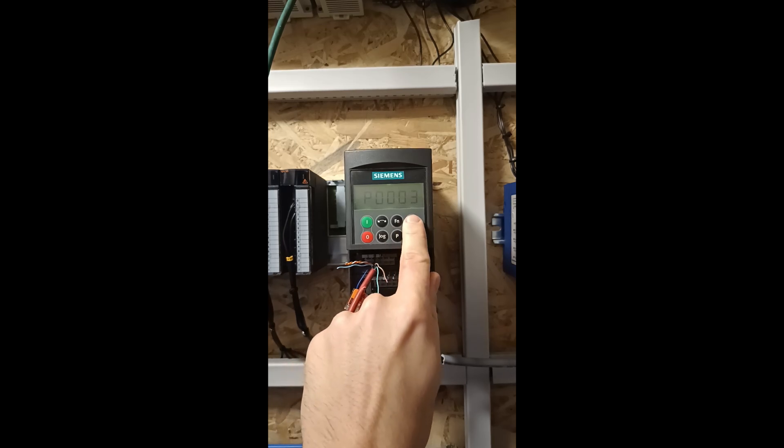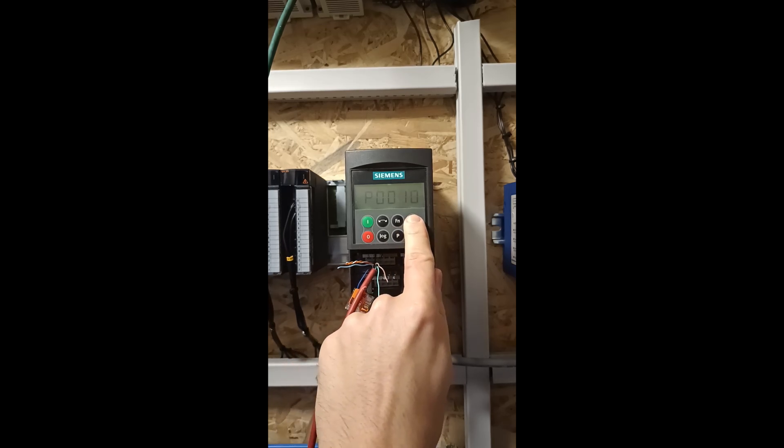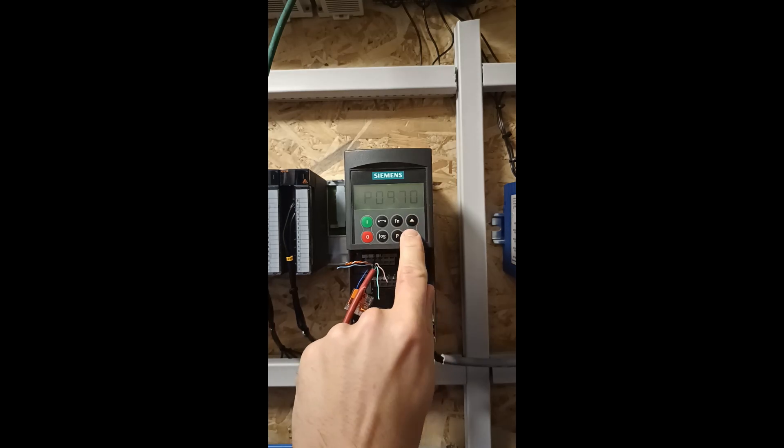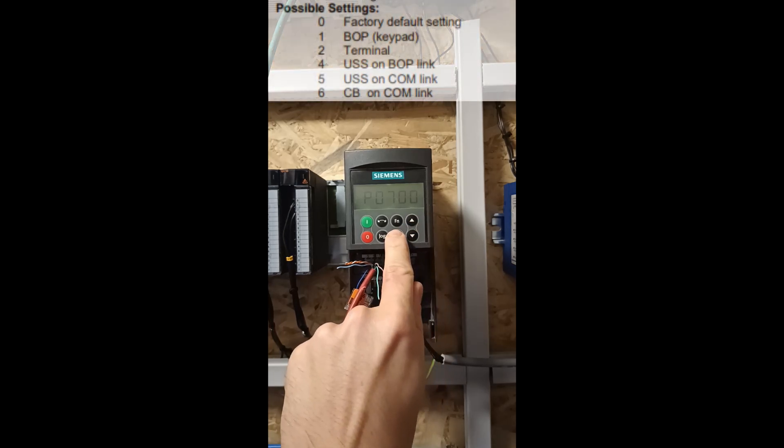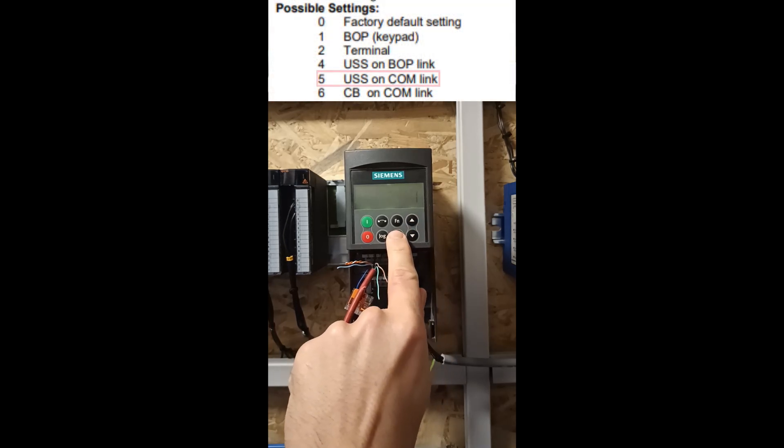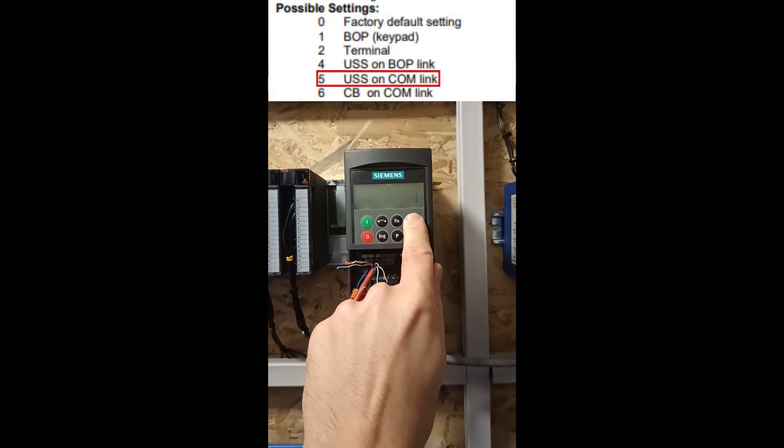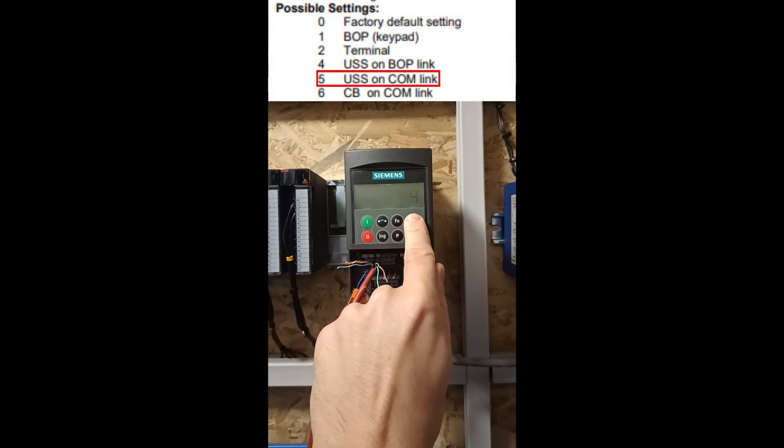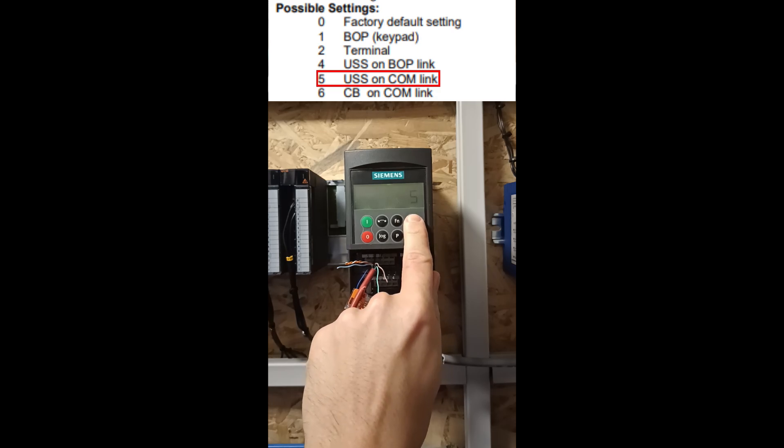Then we want to change parameter 700. I will set it to 5 since it's the USS com link to the command source.